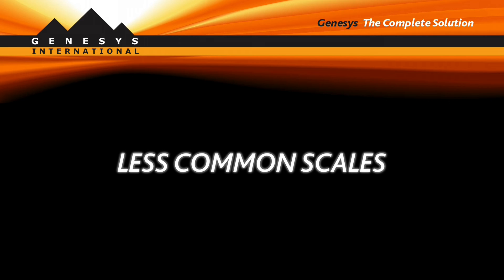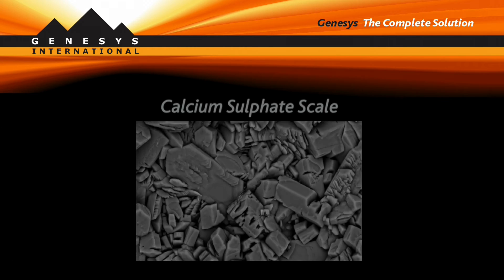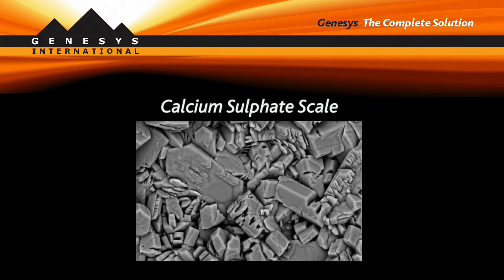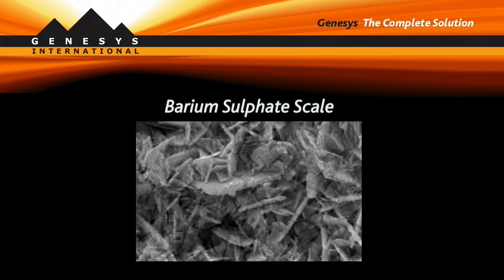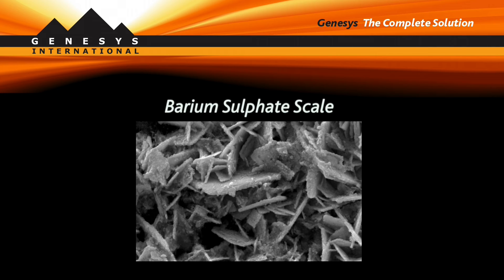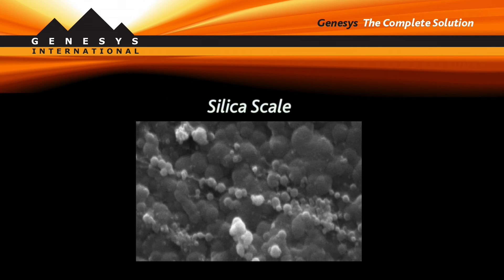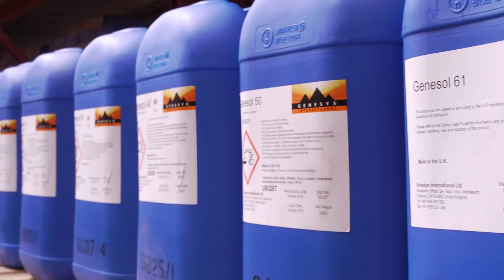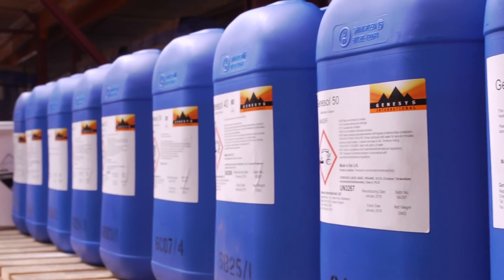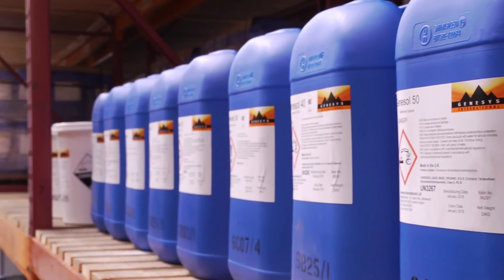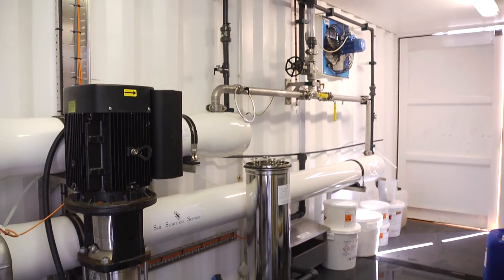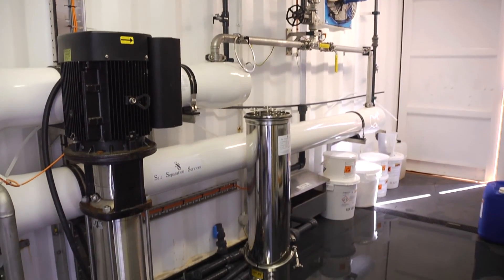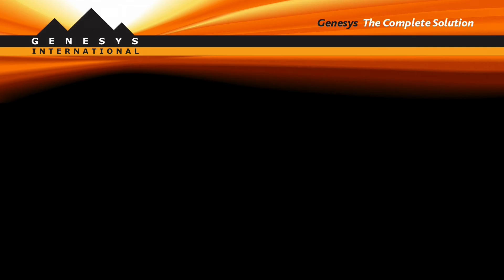Less common scales — calcium sulphate, barium sulphate, and silica are not removed by acids and need a special approach using Genesol 50 chelating agent, combined with long soak times to achieve optimum removal.